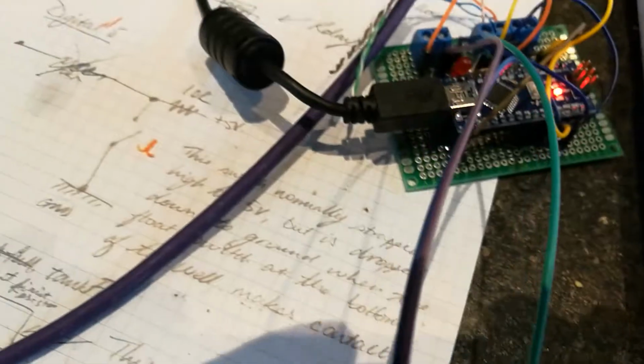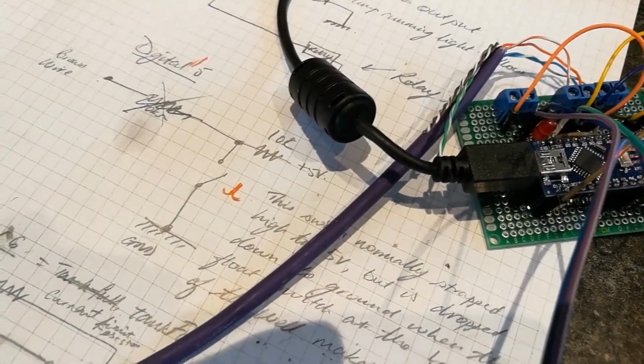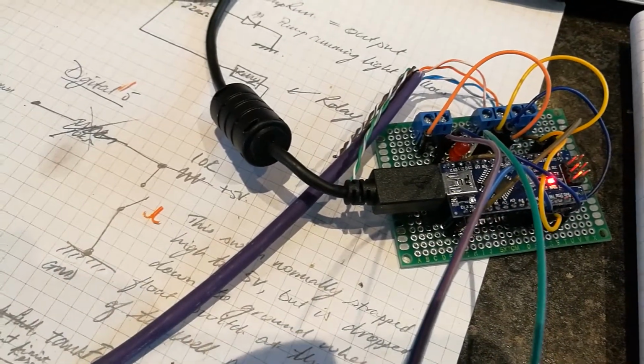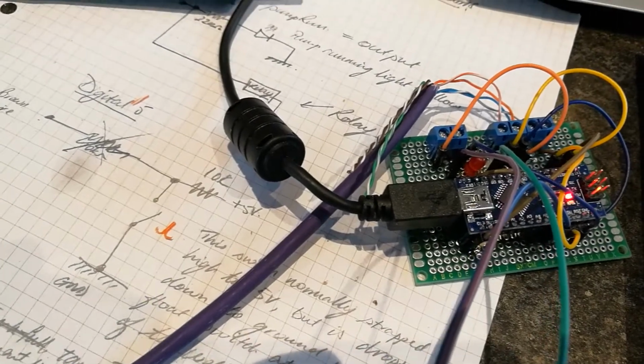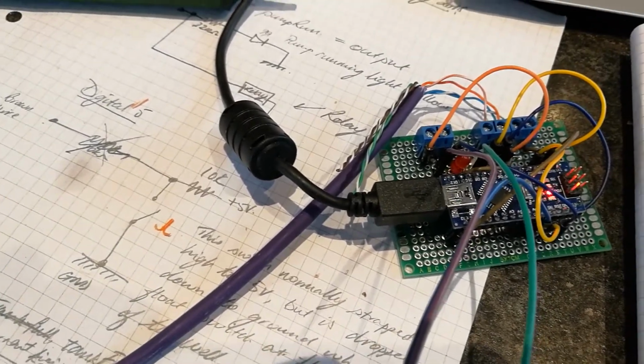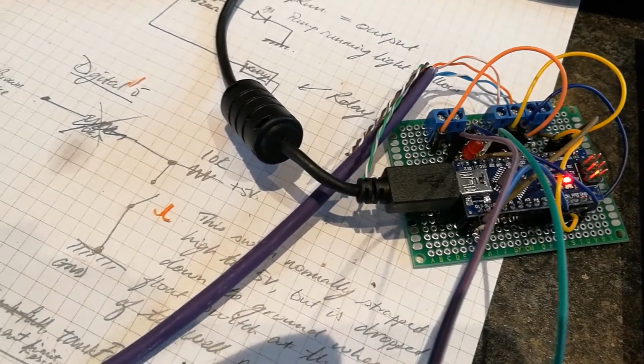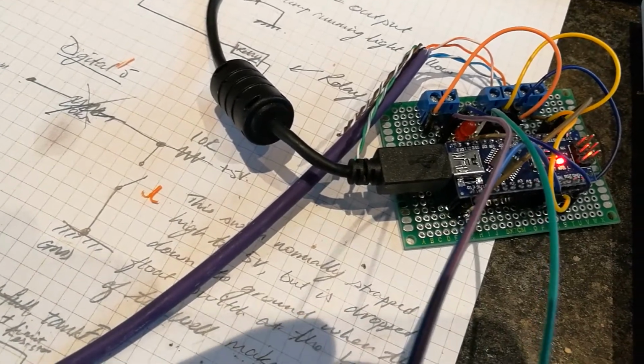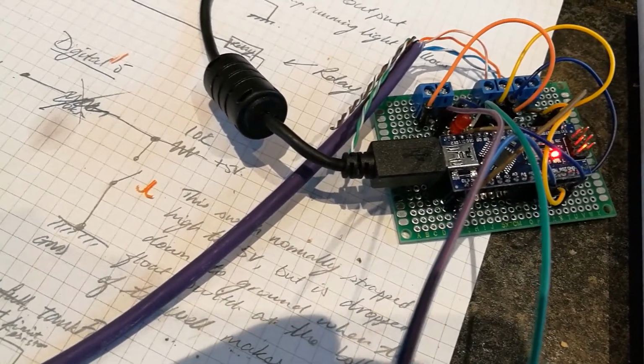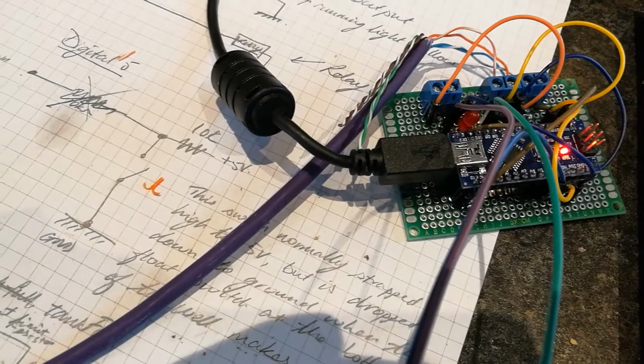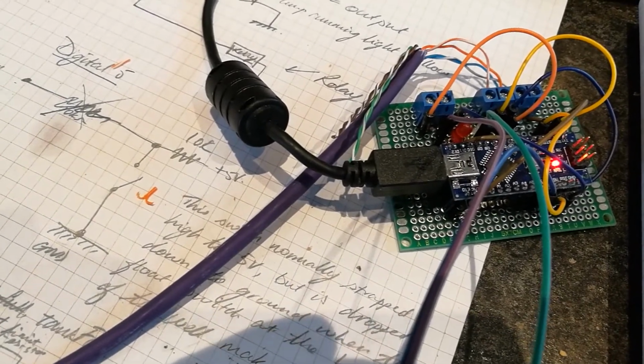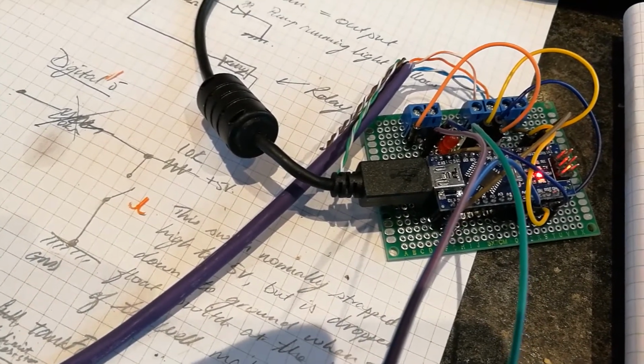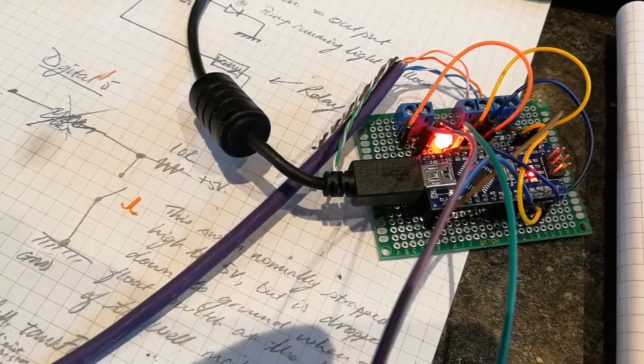Closing the switch, and now there'll be a delay - I can program this delay as long as I want. At the moment I've set it for 30 seconds, so after that, the little red light should come back on, meaning the pump will be back on and pumping water again. When we actually test this, we'll see how long it takes for the well to fill up. And there you go, it comes back on again.